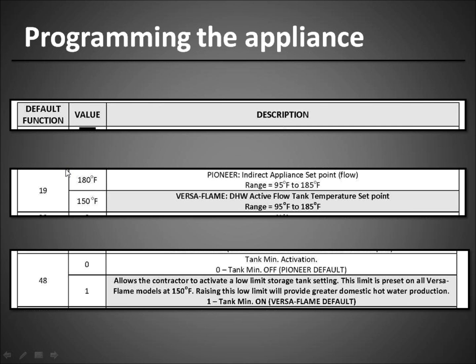In your programming, we now have a low limit, and we have the ability to control the minimum temperature set point with the flame, because on the flame, normally our defaults are going to be what you see here, 180 degrees for the central heating, and then during the summer months, we have to maintain a certain temperature because we're relying on the storage in order to supply instantaneous domestic hot water. So we have a temperature set point, factory default, at 150. The customer can either raise this up or lower it down within these ranges.